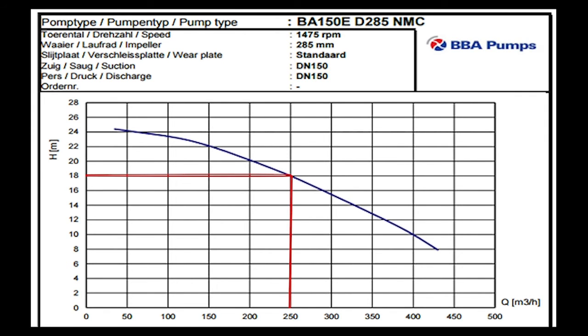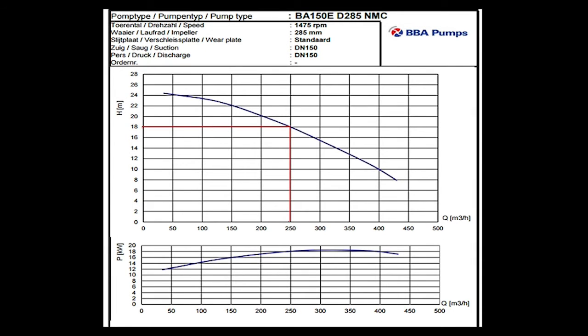From this duty point, we can extend the line vertically to the second segment. Now we can read the absorbed power at the duty point of 250 cubic meters an hour. This is, as you can see, 18 kilowatts. This is important information, for now we know that we need to install a motor of at least 18 kilowatts.